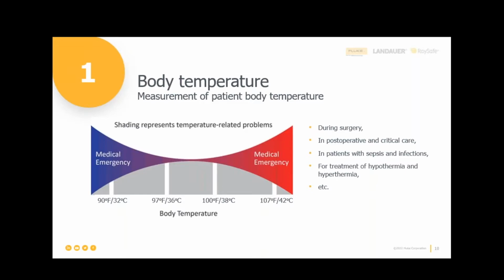Okay, so it is important that we test more than one temperature setting and make sure that it is accurate within the accepted tolerances, right? What are those tolerances? Where do they come from? They come from international standards, and even the AAMI-ANSI standards, which has a standard for every single vital sign, not just the patient monitor alone, right? For every single one of those.